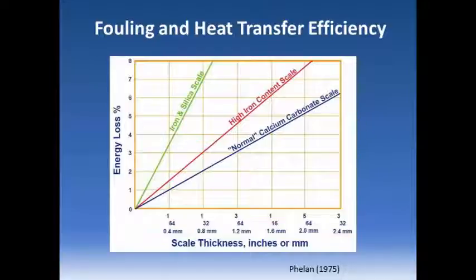Even a very thin film of calcium carbonate can significantly affect heat exchange. This energy loss on the y-axis represents the reduction in heat exchange efficiency. A 2 millimeter film of normal calcium carbonate causes about a 5% reduction in heat transfer efficiency, meaning you'd need roughly 5% more electrical energy into your heat pump to get the same heating or cooling output.